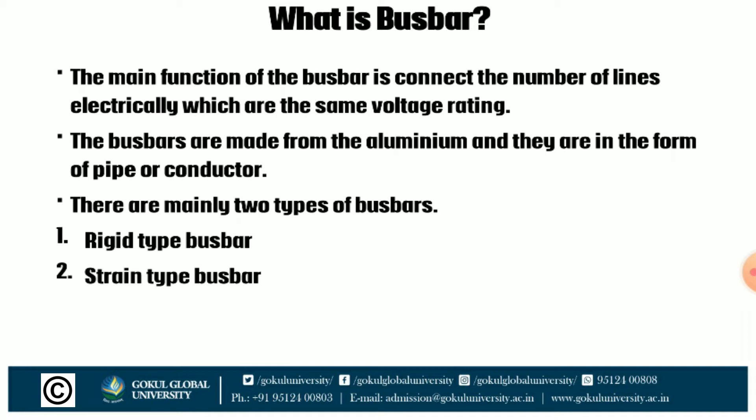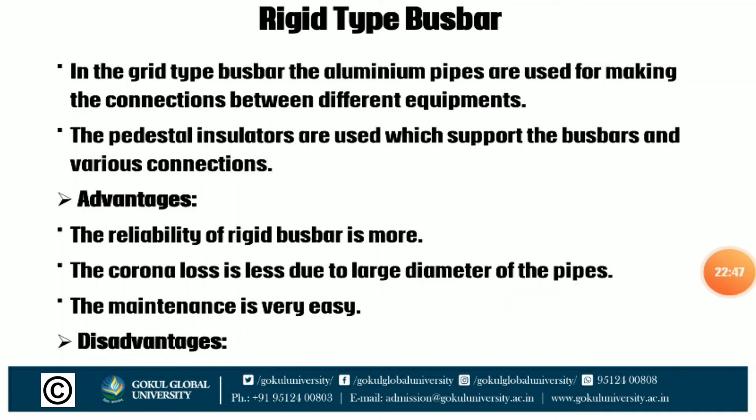Now we discuss about the bus bar. The main function of the bus bar is to connect a number of lines electrically which are at the same voltage rating. Bus bars are made from aluminium in the form of pipe or conductor. There are mainly two types: first, rigid type bus bar; second, strain type bus bar. In rigid type bus bar, aluminium pipes are used for making connections between different equipment, supported by pedestal insulators. Advantages: more reliability, less corona loss due to large diameter of pipes, and easy maintenance. Disadvantages: requires large space and is very costly.